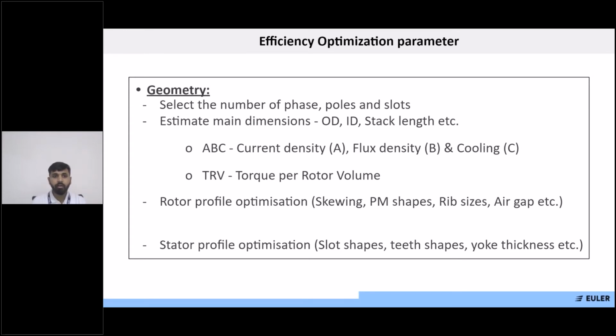Apart from that, when you talk about rotor profile optimization, you decide on your magnet shape, whether V-shape or other, depending upon the harmonic distortion available. According to that, you have to shape your rotor skewing, whether your rotor should be skewed or not. These parameters also depend upon the slots per pole: if it is an integer, you have to skew, and if it is fractional, you don't need to skew.